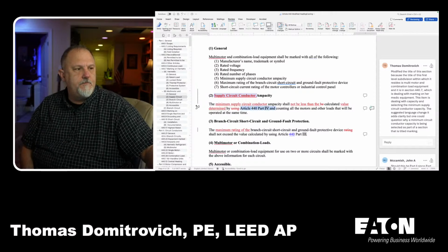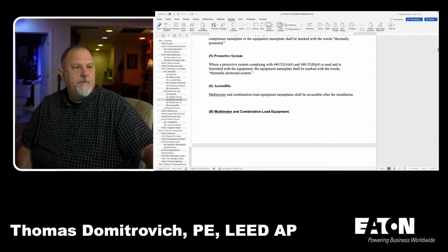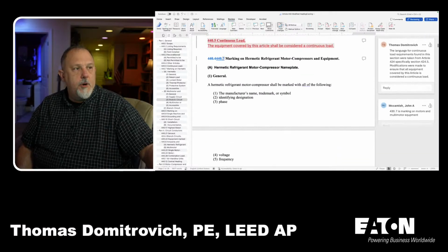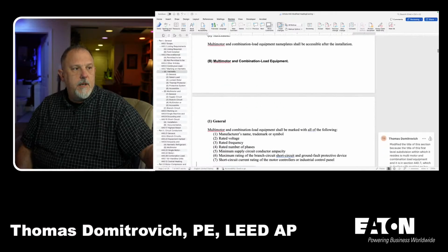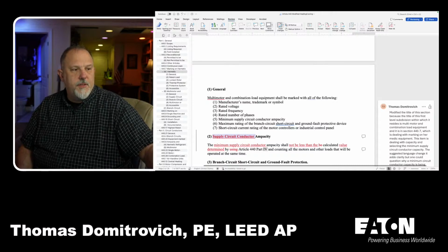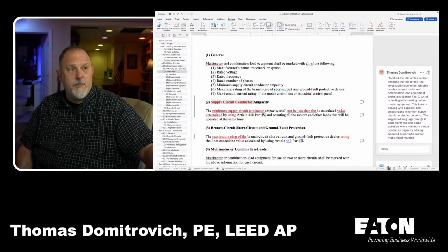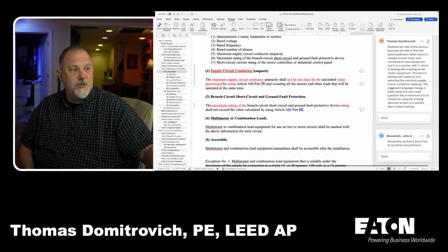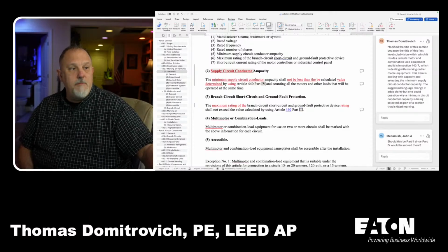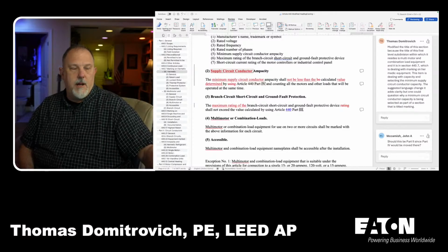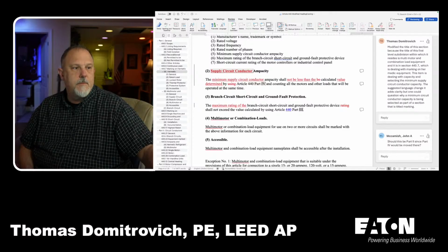There's an Article 440 reference: branch circuit, short circuit. See, this is what's funny, this is in marking on hermetic refrigerant motor compressors and equipment. A is the nameplate. B just says multi-motor and combination load equipment. You get into general, shall be marked with this information, and then it says supply circuit conductor ampacity. It tells you how to calculate the ampacity. It tells you how to determine the maximum rating of the branch circuit, short circuit, and ground fault protection device. Must not exceed. That's not a marking requirement. It's screwed up. But I'm not here to fix that. I'm here to just meld these two articles together.